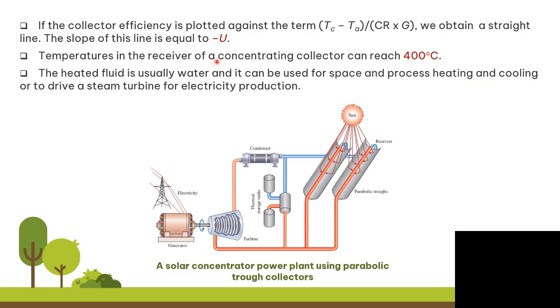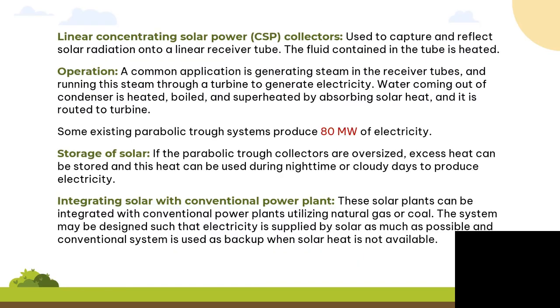The temperature in the receiver of a concentrating collector can reach up to 400 degrees. Linear concentrating solar power (CSP) collectors are used to capture and reflect solar radiation to a linear receiver tube. The fluid contained in the tube is heated — a common application is generating steam in the receiver tubes and running this steam through a turbine to generate electricity. Water coming out of the condenser is heated, boiled, and superheated by absorbing solar heat before being routed to the turbine. Some existing parabolic trough systems produce 80 megawatts of electricity.